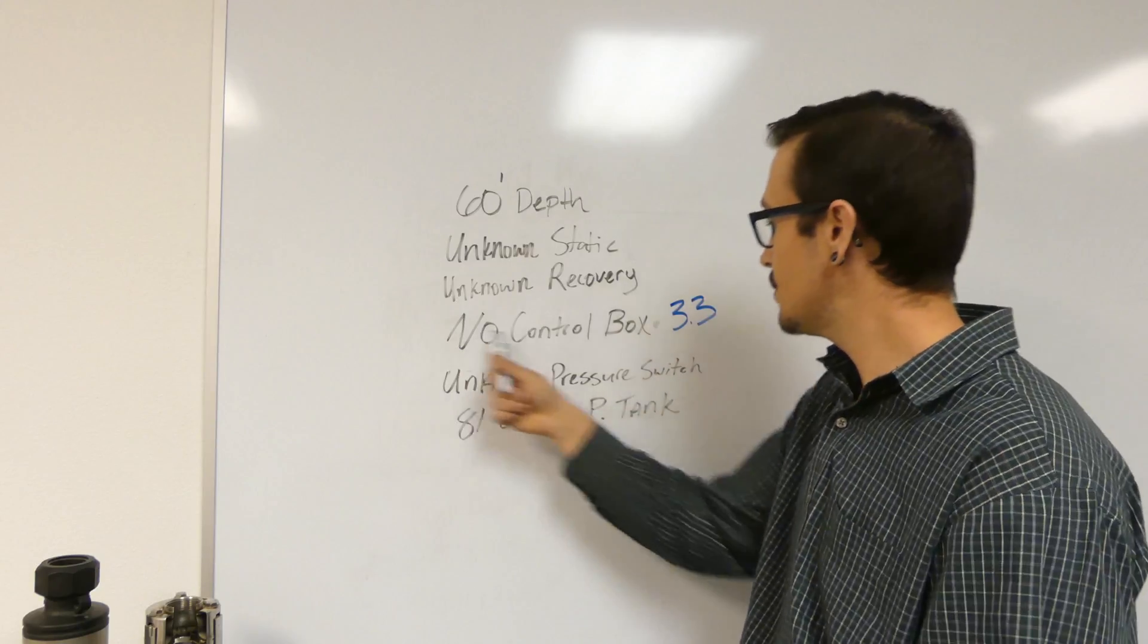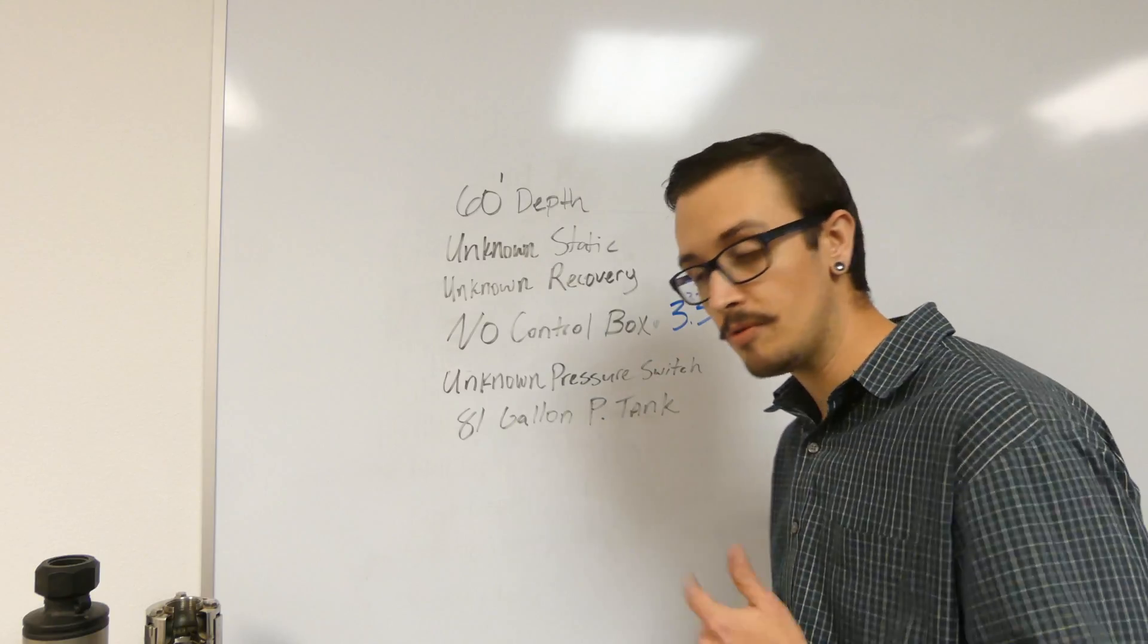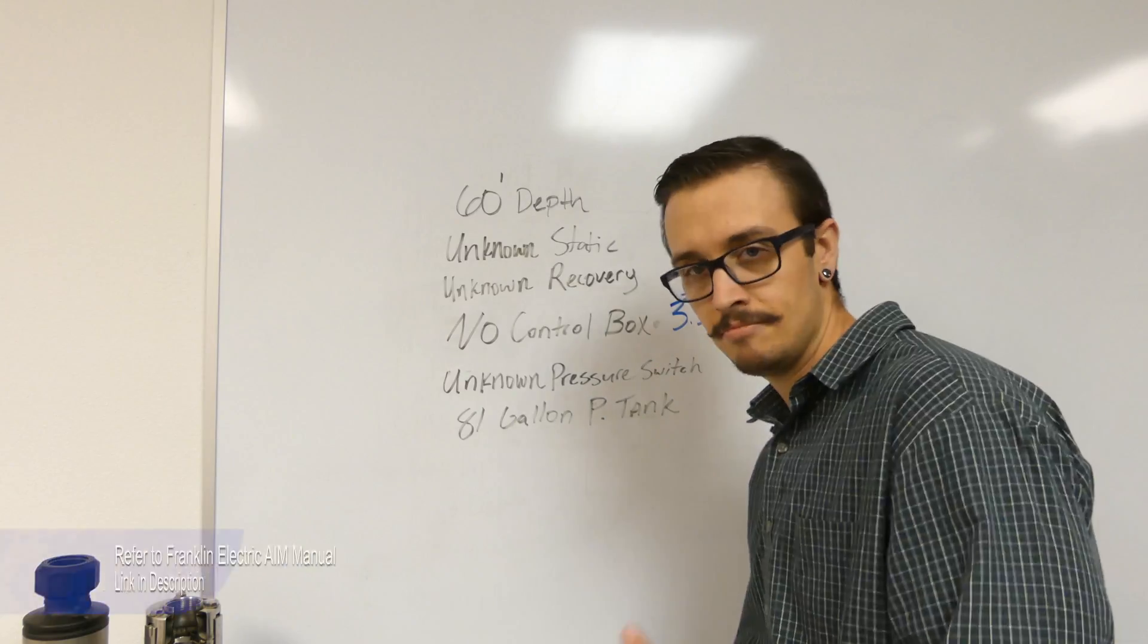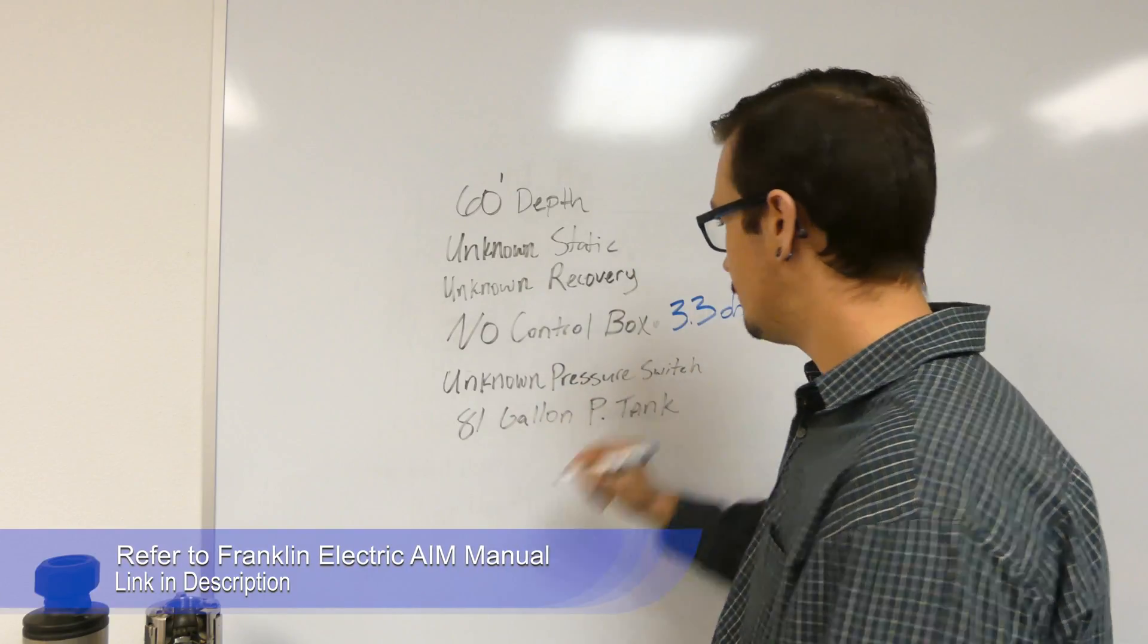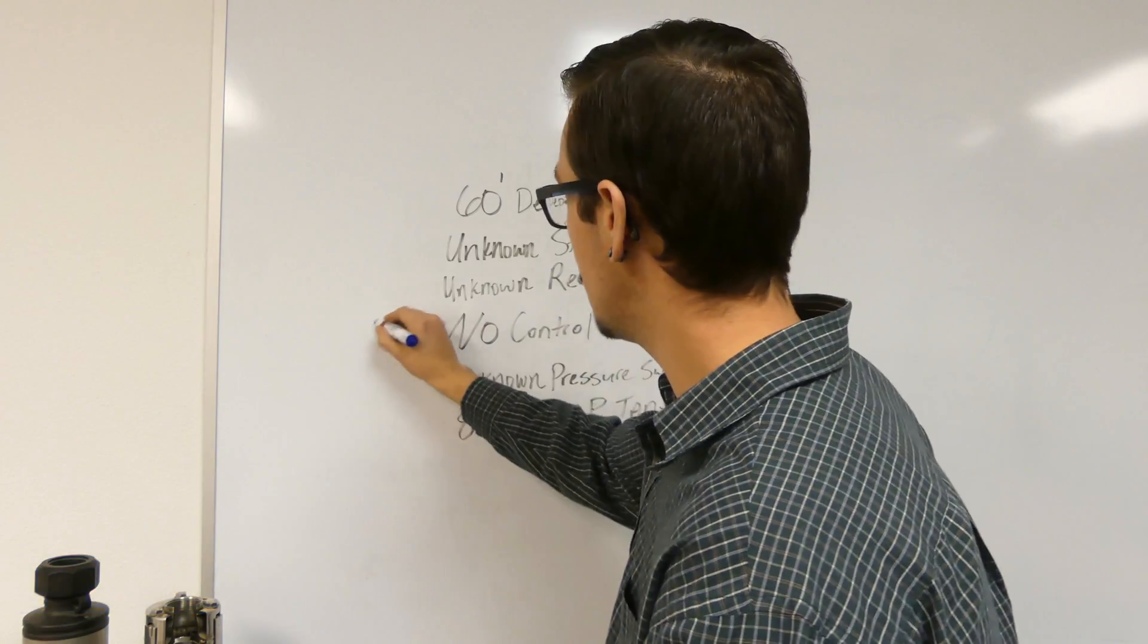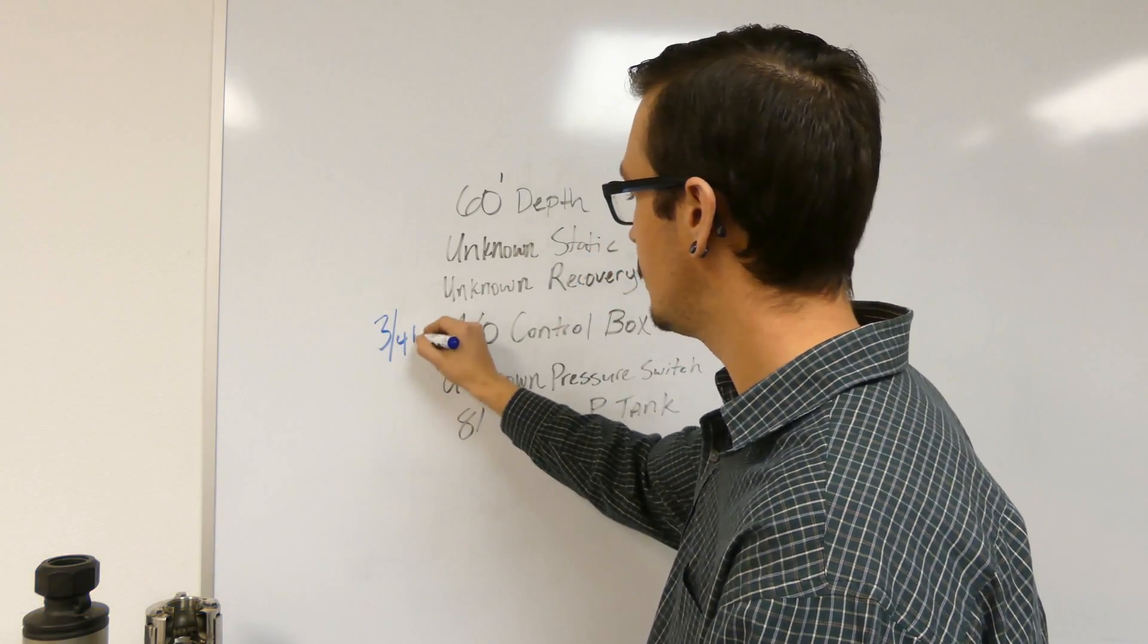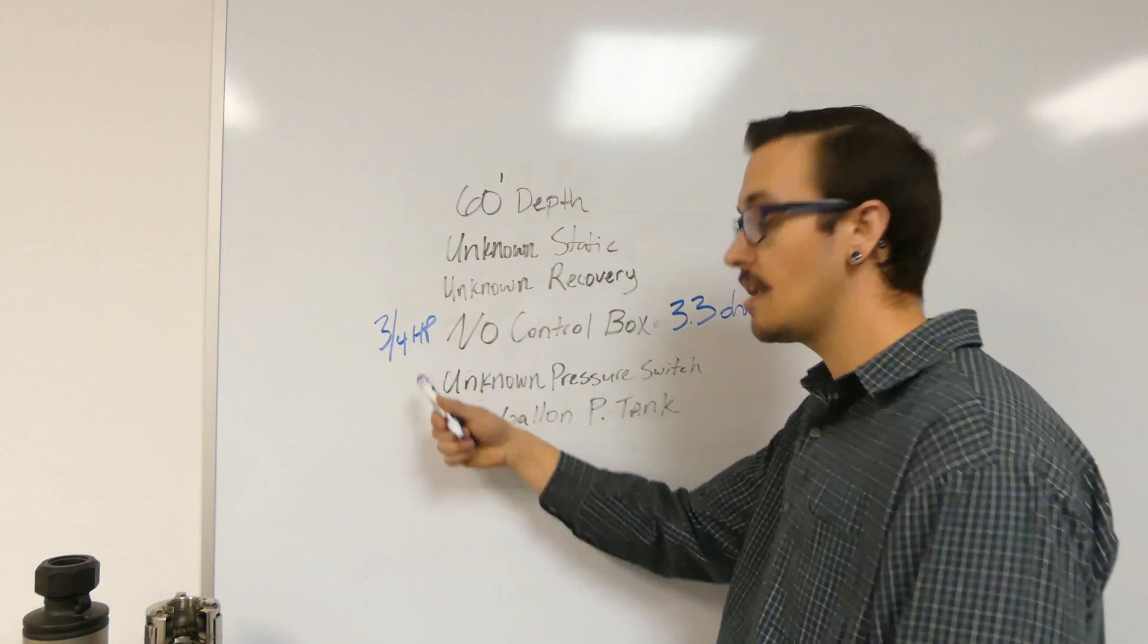No control box, but we took a resistance reading, we got 3.3 ohms. Refer back to that chart in the first section of the video - that means that we have a three-quarter horsepower. So now we know this, and we can assume that with a pretty good level of confidence.